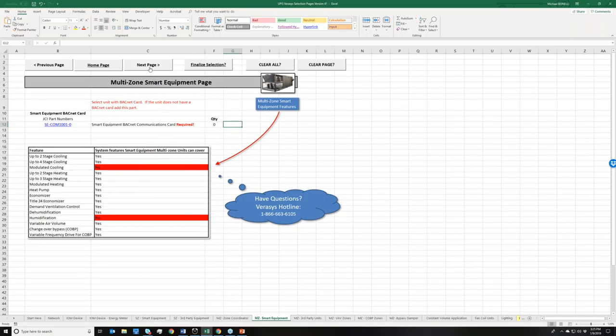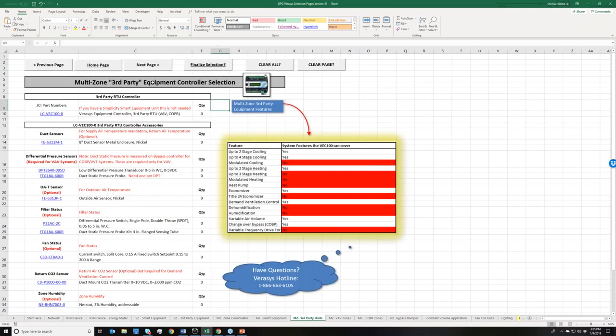I'm going to move on to the next page. This is our third-party zoning system solution, which uses our application controller, part number LCVEC100. It can do VAV or changeover bypass. There's no programming, no programming tool, and no coding. All our Verasys controllers have the programming already installed on the controller itself. All you have to do is connect to the controller and set it up on your phone or smart device, which is pretty nice. There's no licensing fees or anything like that.